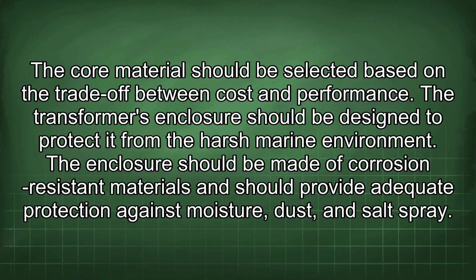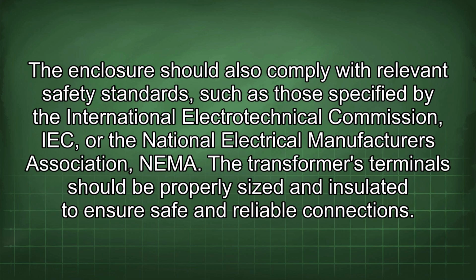The transformer's enclosure should be designed to protect it from the harsh marine environment. The enclosure should be made of corrosion-resistant materials and should provide adequate protection against moisture, dust, and salt spray. The enclosure should also comply with relevant safety standards such as those specified by the International Electrotechnical Commission (IEC) or the National Electrical Manufacturers Association (NEMA).